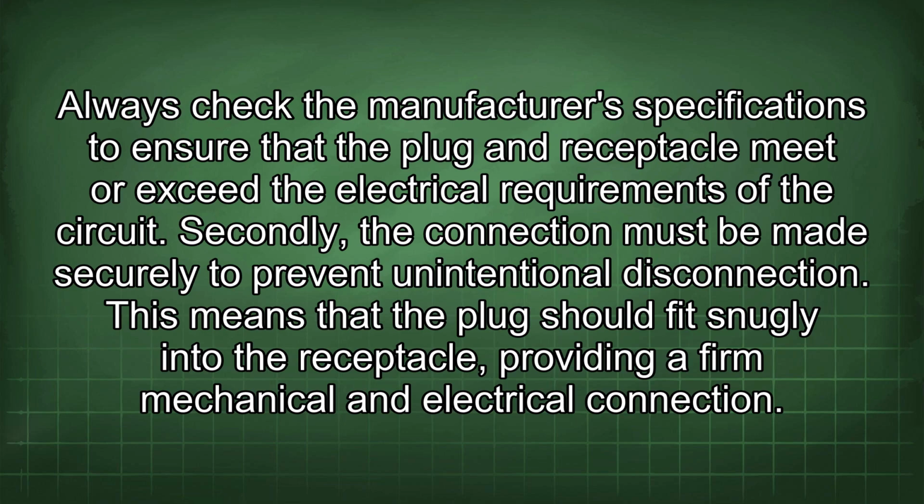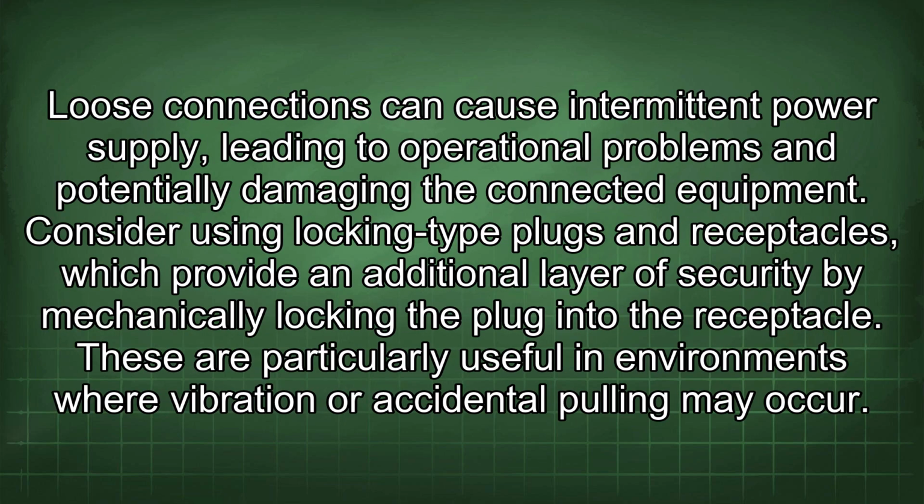This means that the plug should fit snugly into the receptacle, providing a firm mechanical and electrical connection. Loose connections can cause intermittent power supply, leading to operational problems and potentially damaging the connected equipment. Consider using locking-type plugs and receptacles, which provide an additional layer of security by mechanically locking the plug into the receptacle. These are particularly useful in environments where vibration or accidental pulling may occur.